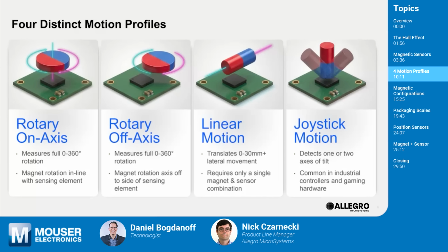Linear motion is just like you see there—the magnet slides by back and forth, usually using a rod magnet. Again, the size is about half of the stroke length; that gets you your best nonlinearity and best accuracy. You can go smaller or bigger, depending on the constraints of the system. That gets you about 0 to 30 millimeters.